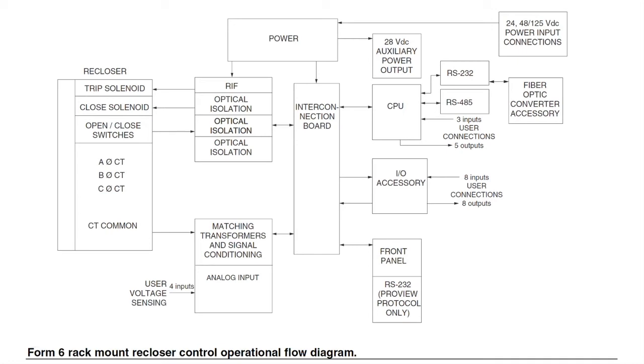Line current flowing through the recloser is converted by the CPU module to a digital signal suitable for metering and fault current calculations. Data sampling occurs at a rate of 64 times per cycle. The CPU contains a data acquisition section that uses the acquired samples to compute the fundamental currents and voltage for use in overcurrent, under-over-voltage, and under-over-frequency protection, as well as currents and voltages for metering functions. The current for overcurrent protection is calculated on a sub-cycle basis. It includes only the fundamental and DC component.